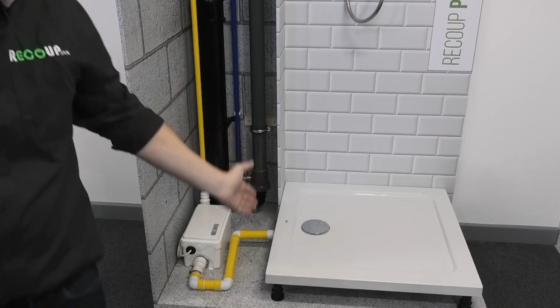So we have added a component here that requires electrical feeds to it, and also has a serviceable requirement in line with Saniflo's service requirements for it, which I believe is a biannual flush through descaler, which does mean that this unit does need to be in an accessible position. So you're probably likely to see it in this sort of configuration here, where you've got the shower tray and you've got this void behind the shower here, where you can site that vertical pipe towards the back, grey water pump towards the front there, and you may have to have an access panel towards the front here. Now, the trap that's actually supplied with this is a very low profile trap as well, so obviously you're going to require a fall into that pump itself, but you can achieve that at quite low tray height installations if you can site that pump really close to the outlet as well.